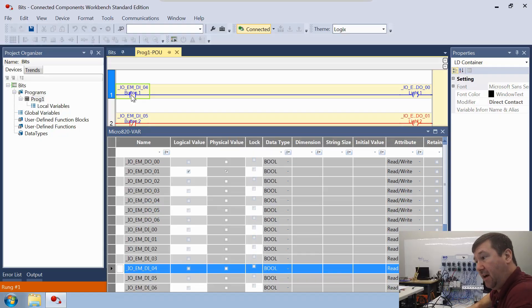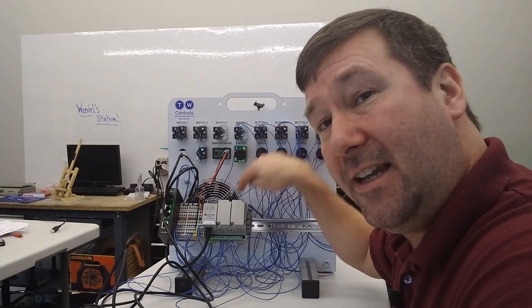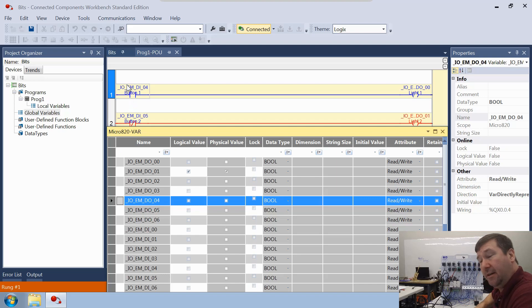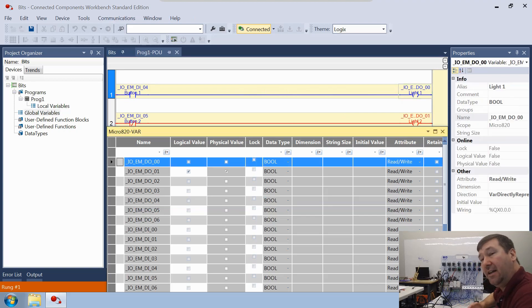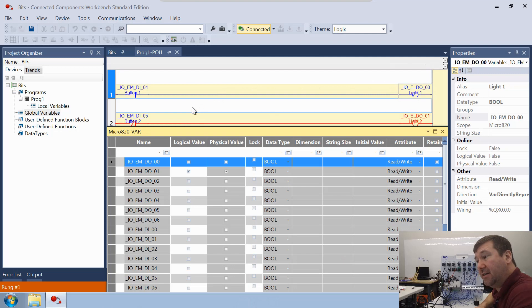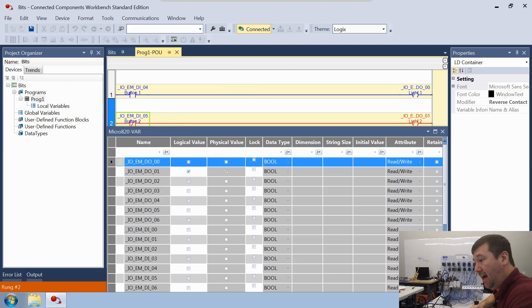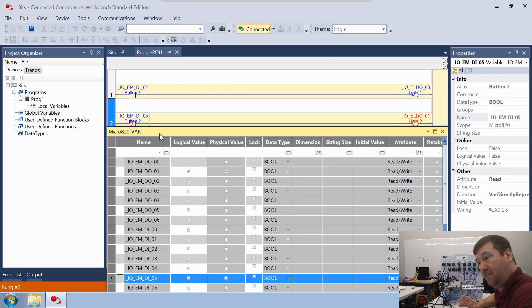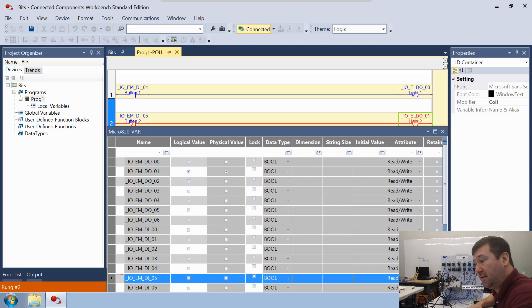It's going to come to this instruction and say, do I have a 1 at Input 4? Now it's very important to realize this is looking at Input 4 in your global variable — it is not looking at the physical input. It looks there and says I have a 0; it was looking for a 1, so this is false, and it passes a false condition to this coil. A false coil writes a 0 to Output 0 — again, only to the global variable, not the physical output. Then it goes to the next rung. The Reverse Contact says go look for a 0 at Input 5 — it found a 0, so this is true. It passes true conditions to the coil, and a true coil writes a 1 to Output 1. Again, only to the global variable.